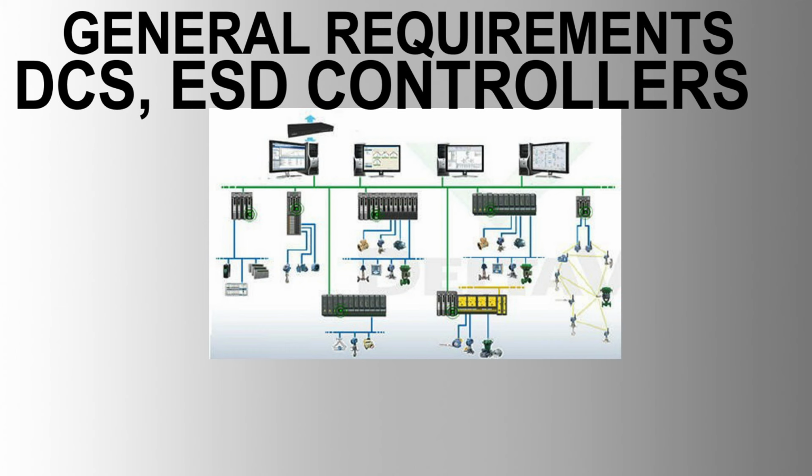10. Relays and interface cabinets. Relays. High-grade relays should be used for emergency shutdown functions. Relays must be SIL certified, preferably to SIL 2 or 3, to ensure reliability and safety. Interface cabinets. Cabinets should house relays and other interface components. Design should allow for easy access and maintenance.